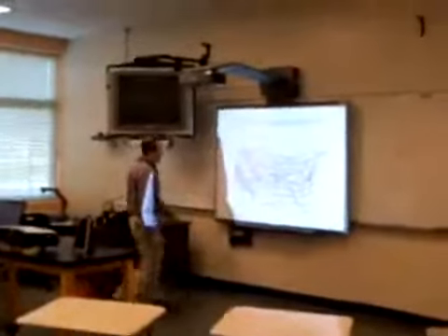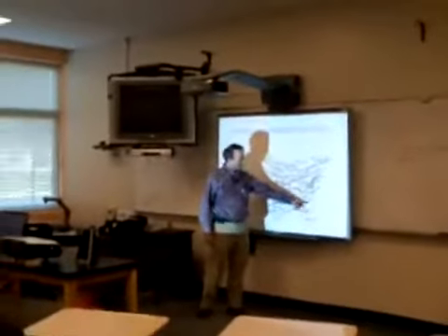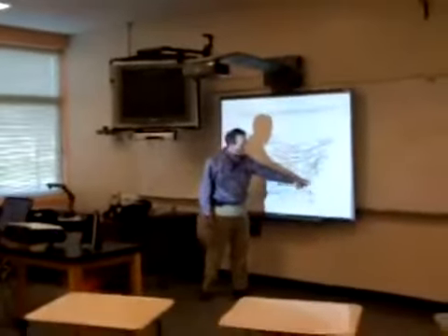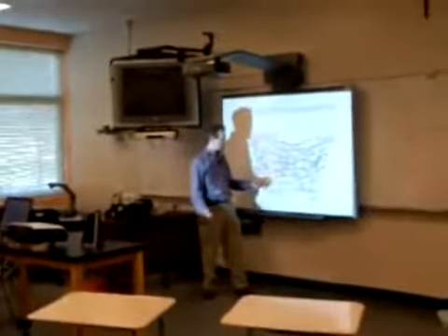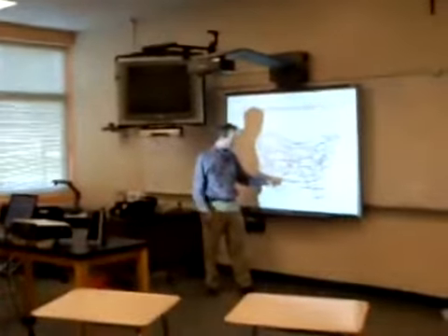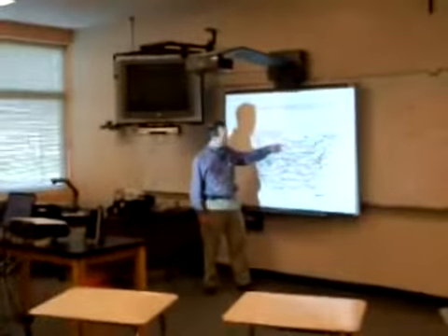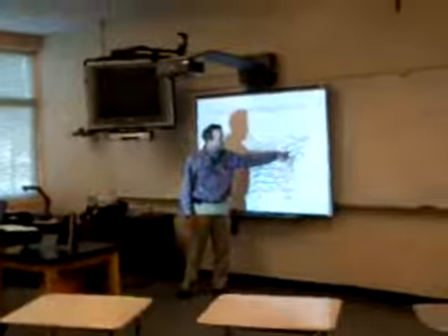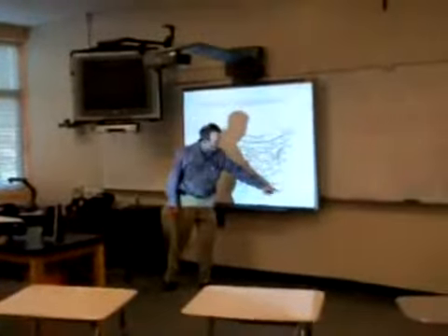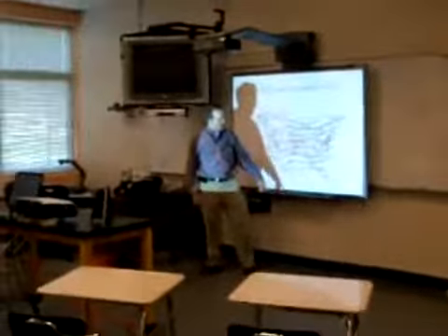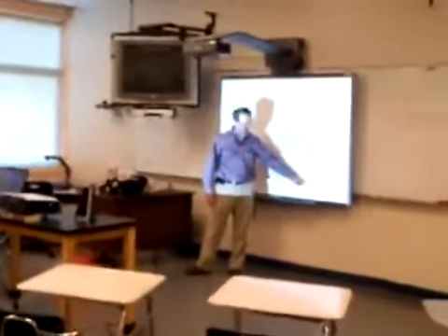Okay, this tells you the ground is 67 degrees year-round, right where we are. I said 75, I was wrong. But as you go up north, the ground gets colder. It's 47 degrees up in New York, and it's 77 degrees way down in Florida. So geothermal is not as good down here because it's very hot and the ground's warm.